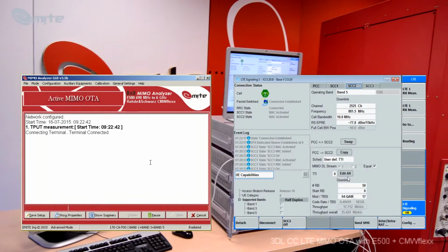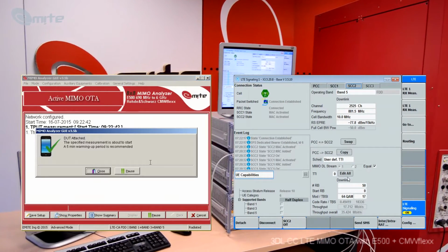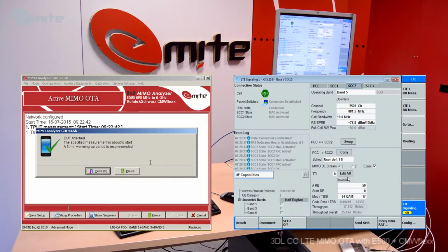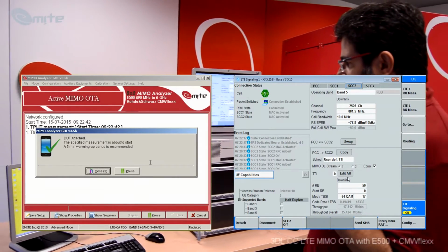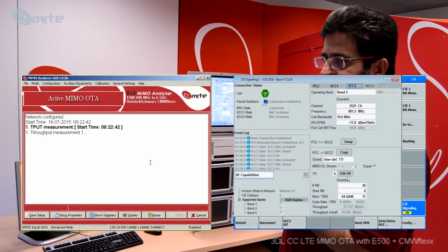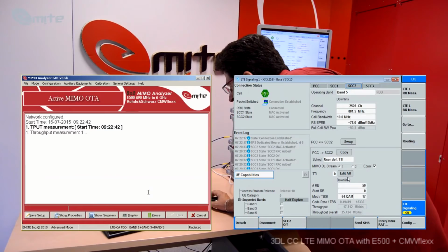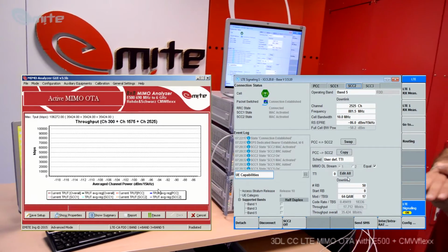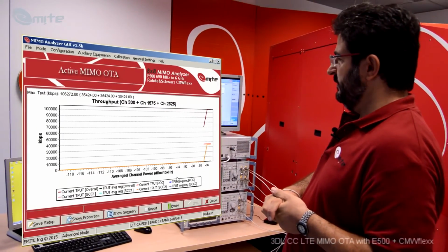Connection has been established, and there you go. There's a choice to have a warming up period for the device so as to have the same setting conditions for the test, and then you can check the measurements in text format like this one, or display format here.